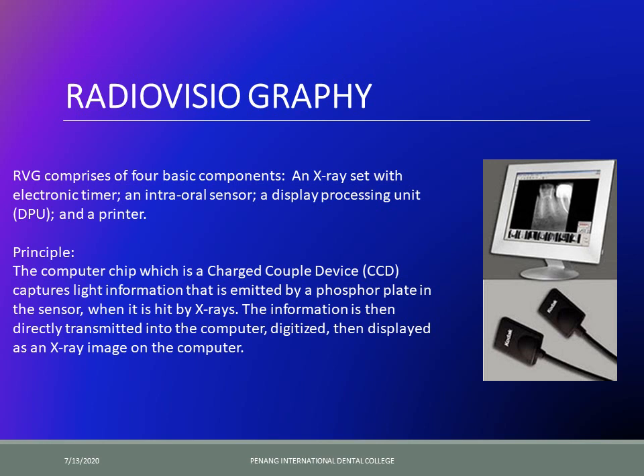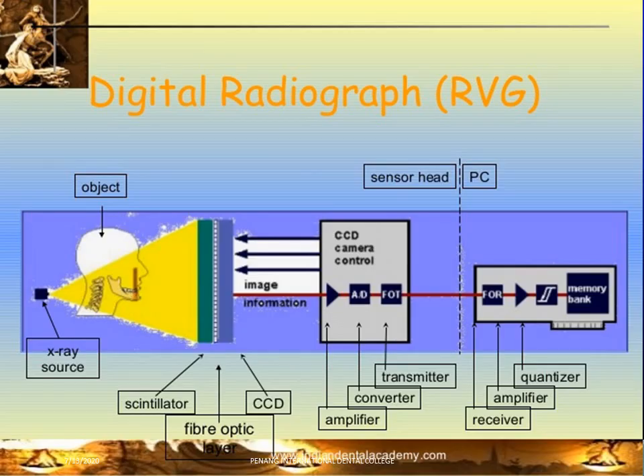The intraoral sensor is composed of a charged coupled device which captures light emitted from a phosphor plate placed just behind the sensor when hit by x-rays. As soon as x-rays hit the phosphor plate it emits light, which is captured by the charged coupled device, then transmitted to the computer, digitized, and displayed as an image on the computer screen. This is how the radiovisiograph works.